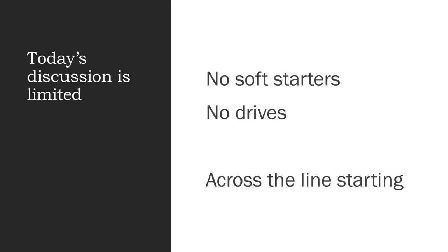The discussion today, and when you get into deep discussions about start inhibit, and those kind of things, we're really talking about across the line starting. It's not that our discussion doesn't apply to soft starters or drives. It's just a much more major factor when we are attempting to start motors across the line. I have already begun preparing for a webinar sometime in August in which we will discuss specifically the protection of motors when a variable frequency drive is utilized.